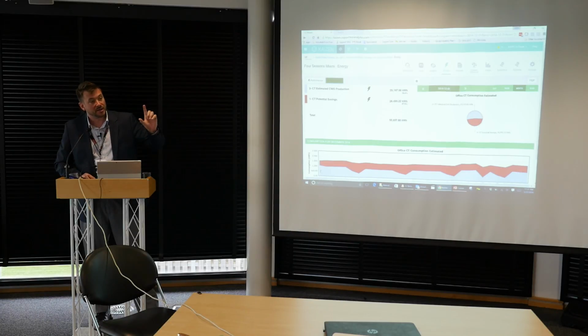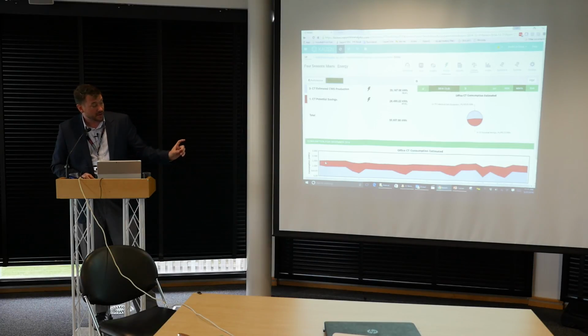And we imported the performance curve of new pumps. So we had some pumps in mind that we said these are variable speed pumps that you should use. At the same flow rates being demanded by the building, those pump curves were imported, and that's what the energy used would be, which is what's blue. So essentially the red is what you would save every month.